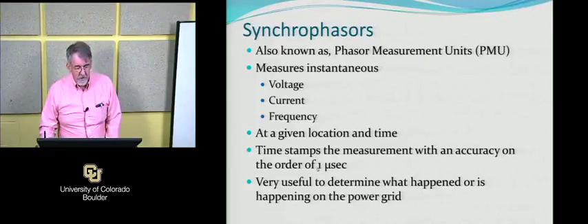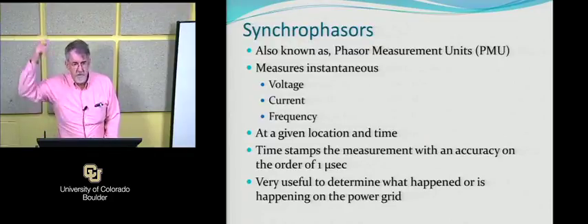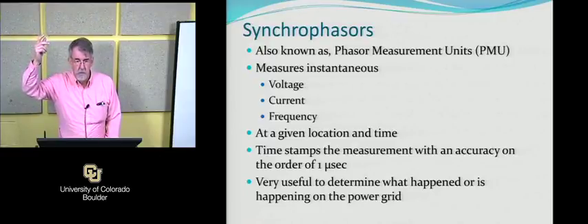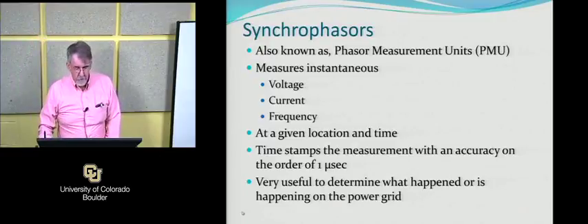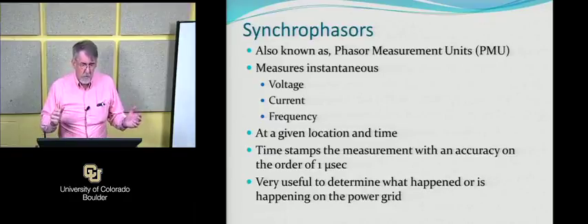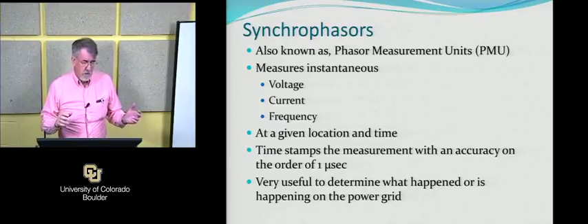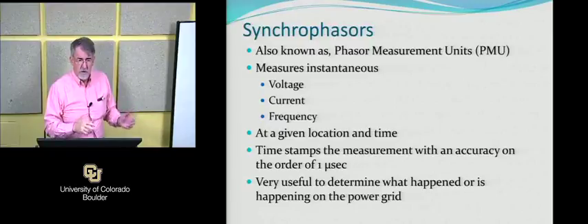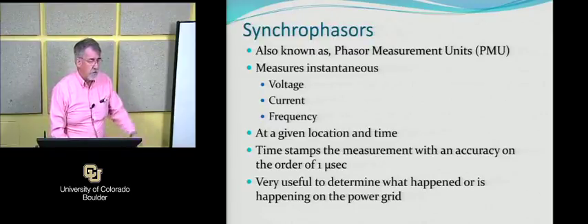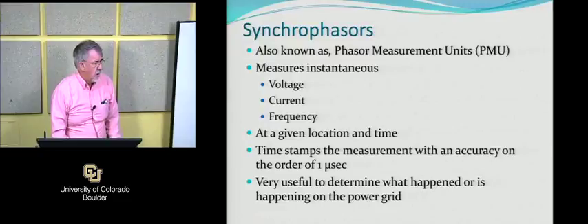The other interesting thing about this 1 microsecond is because of it, there's whole new standards or whole new protocols for measuring time. And it's synchronized to GPS satellites. Okay? But in order to get that 1 microsecond, because if you don't get that 1 microsecond, the error in your voltage and current frequency readings is too big, and you can't tell what's going on. Yeah, Cam? It's very useful to determine what happened on the grid.